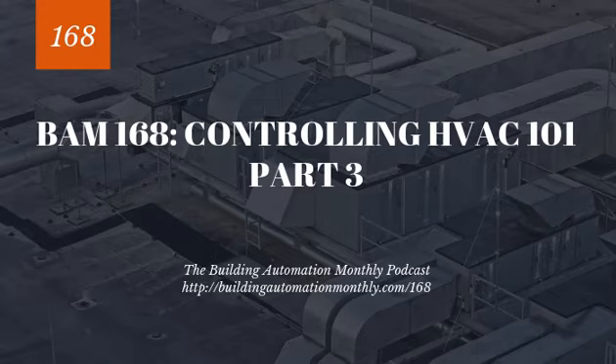Now, the other thing I want to talk about here before I get into air-cooled chillers and water-cooled chillers and how to control and sequence them is two concepts that a lot of folks still don't really understand, and that is lift and load. You oftentimes will hear these terms used, and sometimes folks will use them incorrectly. So the easiest term is load, and it's a percentage of the performance of a chiller. So it's how much the chiller is loaded.